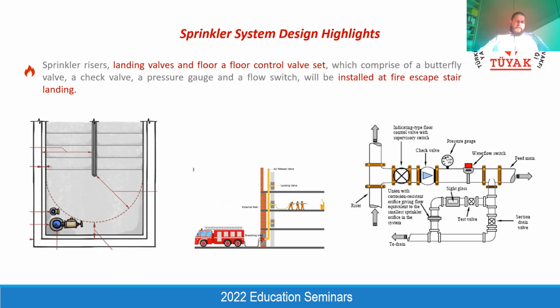And also, when we have a water-based suppression system, when we have sprinklers, landing valves and fire hoses, we should have risers within the staircases. Most of the architects are requiring to locate these risers in the mechanical shafts, but it is not convenient. As per the Turkish fire code and also as per international standards, these landing valves and also these risers, meaning the main pipeline taking the water to the upper levels. You can see there, this is a pipeline passing through the landing of the fire escape stairs.